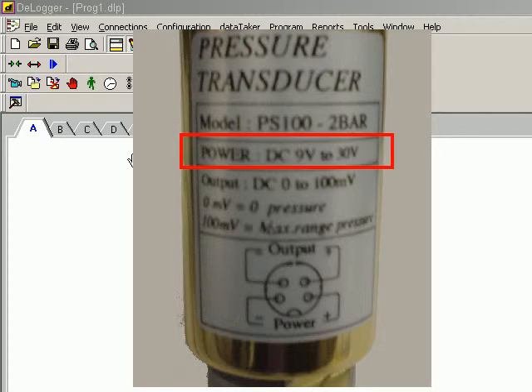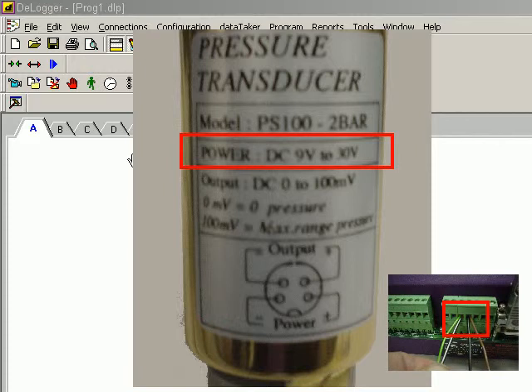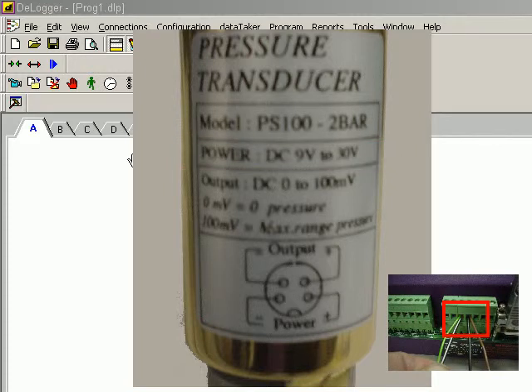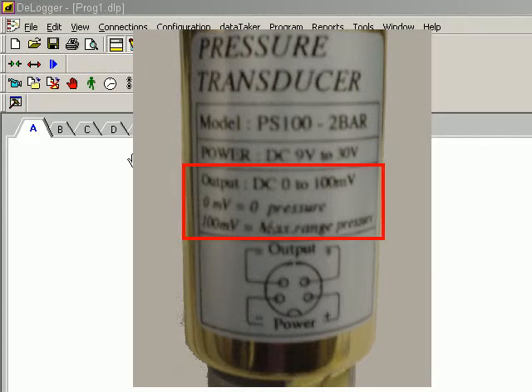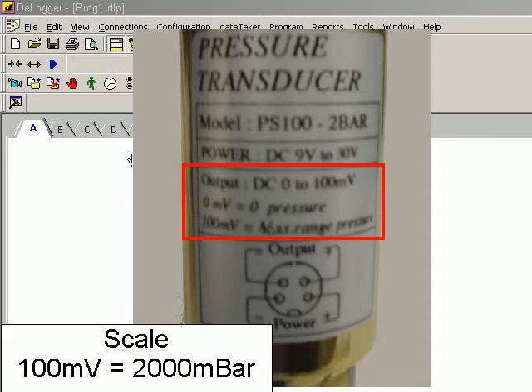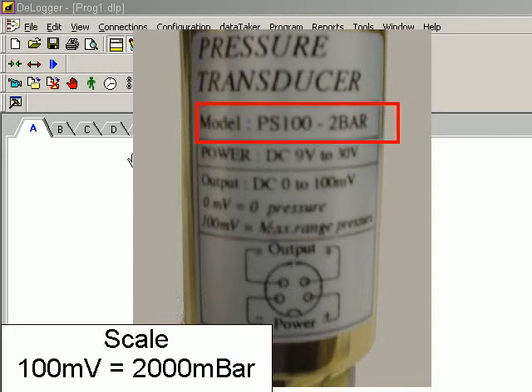This can be provided by the logger power supply. The output is scaled to 100 millivolt, and that's equivalent to 2 bar, or in this case I'm going to scale that to 2000 millibar.